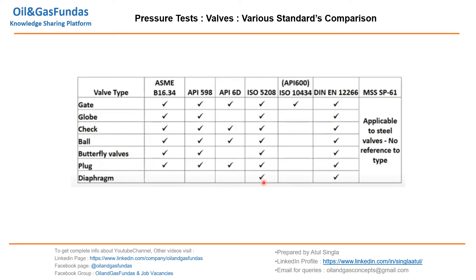ISO 5208 states the shell pressure test is required for all valves. API 600 covers gate valves only. As per DIN 12266, it is required for all valves. MSS SP 61 is applicable to steel valves with no reference to other types. This is a comparison about valve inspection and testing related to the clauses given in these standards, specifically regarding the shell pressure test.